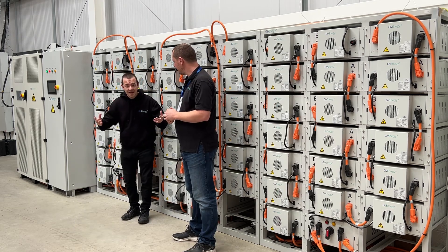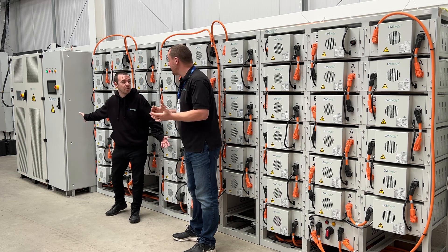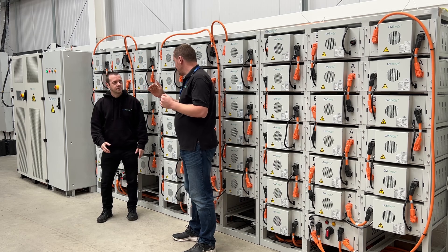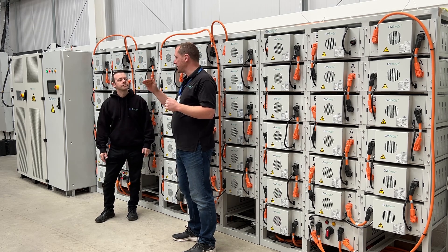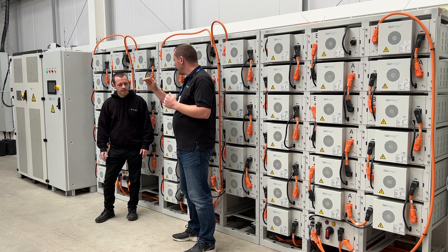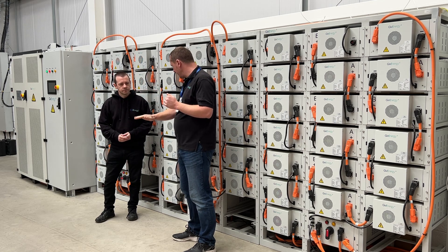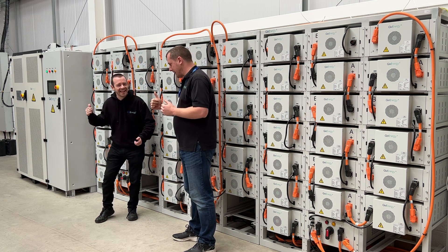You can probably hear a big fan kicking in on the inverter. What's that doing? Cooling it down. The fan is dynamic — it's not on all the time. It will come on as and when required. When the internal temperature gets to about 50 degrees it will kick in, and when the internal temperature gets back down to 30 it will shut off and carry on.